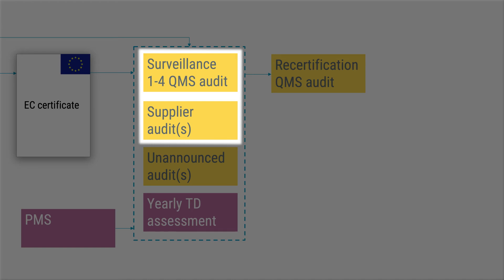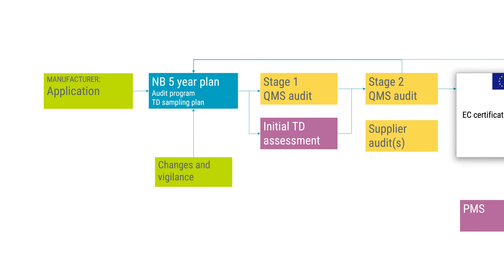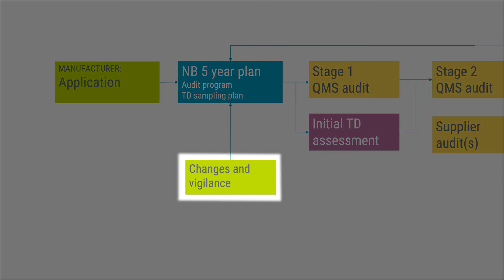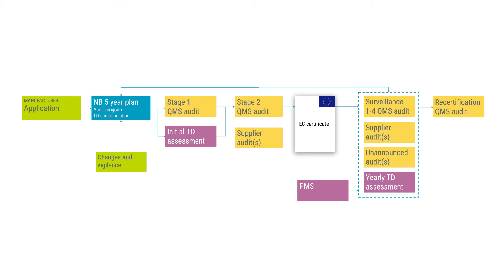The coming surveillance audits shall be done within 12 months after the previous audit. These surveillance audits shall also cover potential critical supplier audits as decided and included in the notified body's audit program. A supplier audit can also be required with the initial stage two audit. At least one unannounced audit shall be done by the notified body during each certification cycle. The manufacturer is obliged to report changes in their QMS and product portfolio to the notified body. Any potential vigilance events and the mandatory PSURs shall also be reported to the notified body. All this information serves as input to the notified body's 5-year plan and can be potential triggers for extra TD assessments, special assessments, extra audits, or even unannounced audits — which can also be conducted at the manufacturer's critical suppliers.